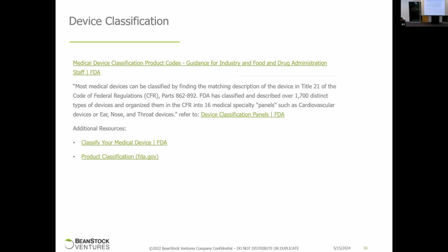This is the FDA legal definition of the device classification. So most devices can be classified by finding a matching description in Title 21 of the CFR. So that's the regulation, and there's over 1,700 distinct device types. I believe with the previous presentation, there were some conversations around how to classify your device by looking at the FDA database. There's no real direct way of doing that other than doing some research. You need to check what your competitors are doing, check the FDA website, and access these links to see if similar products have been cleared by the FDA.